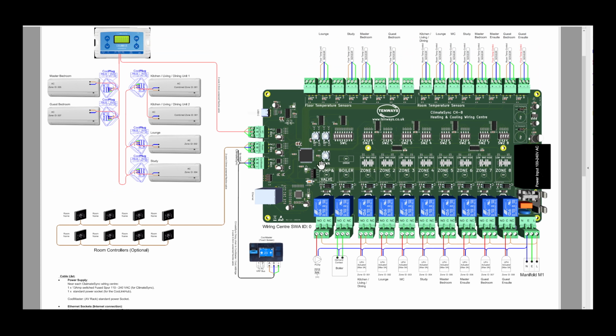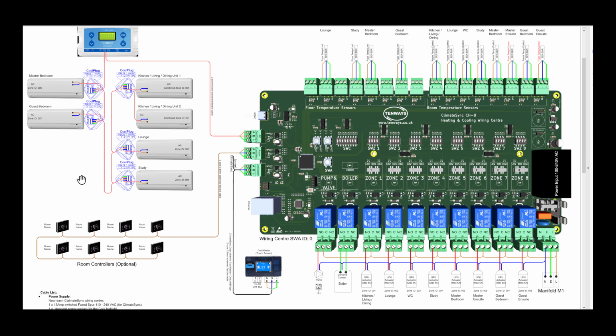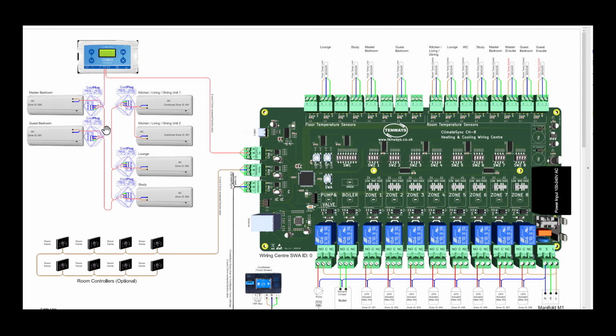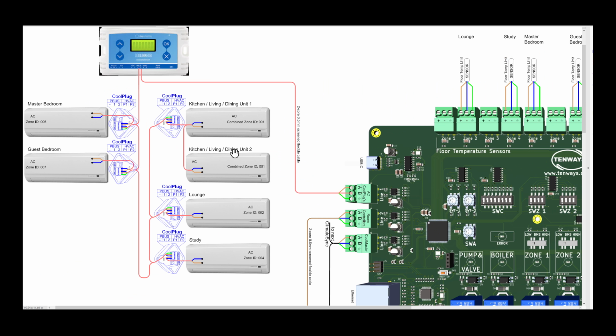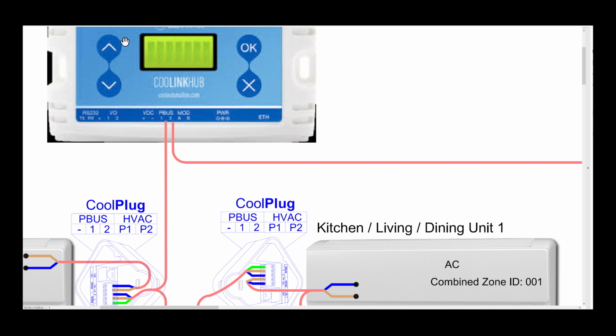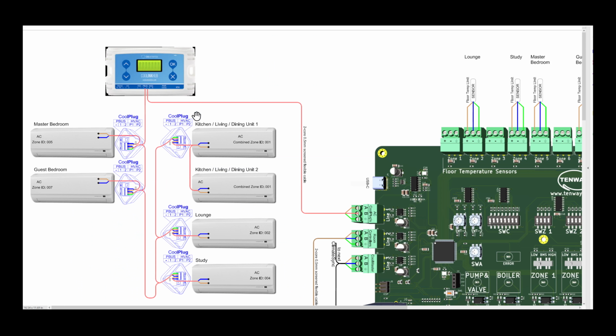Now let's have a look at the communication between the wiring center and the air conditioning. So as we can see over here, we have a 0.5 millimeter 2-core screened flexible cable which goes to a CoolLink Hub, and then the same cable continues from the CoolLink Hub on a different connection. So if you look at the CoolLink Hub, you will see it goes into Modbus, Mod A and B from the wiring center, and then P-bus goes from the CoolLink Hub down to the CoolPlugs by the aircon indoor units.